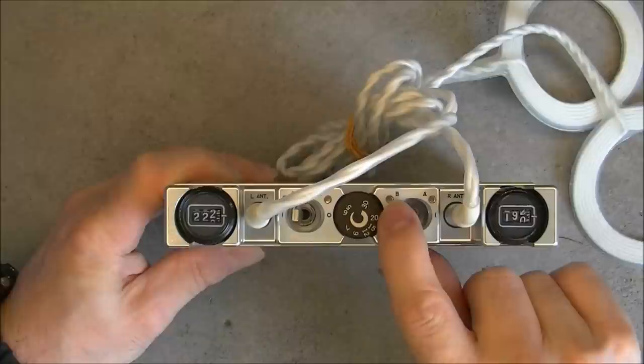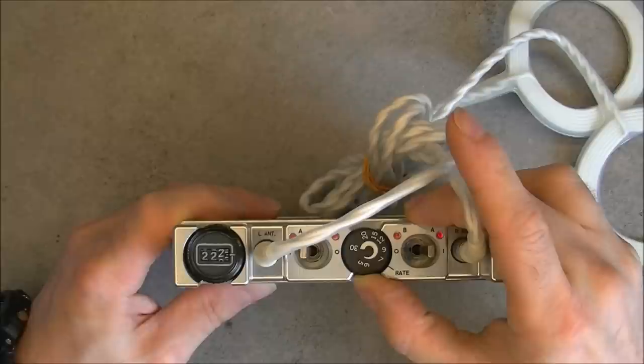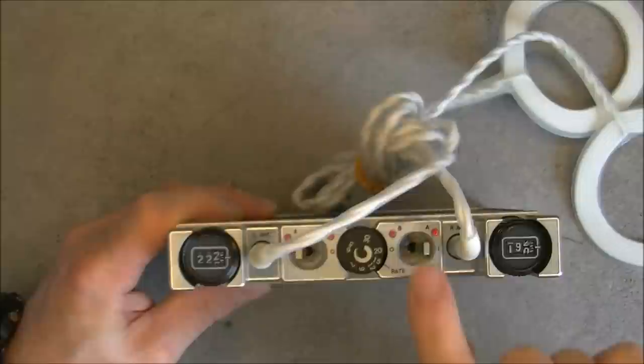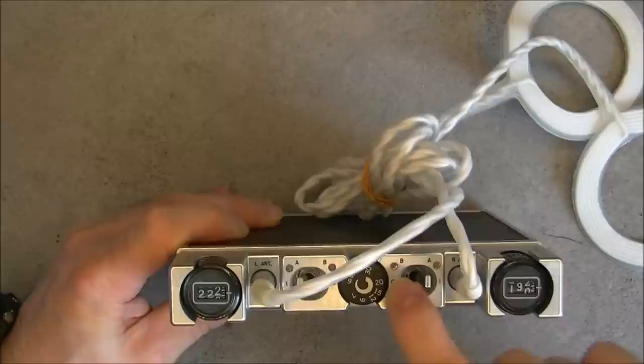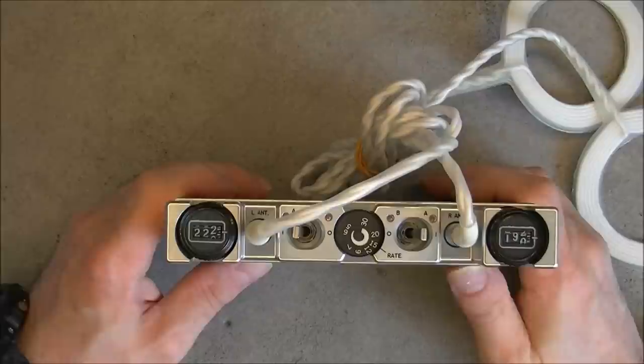So if I power it on in a normal condition as you can see the A and B lights will blink together according to the rate you did set. If you have a battery problem it looks like the B light will not turn on but it is not something you want in a medical device that you have a battery failing without previous warning. So it is a little bit odd.